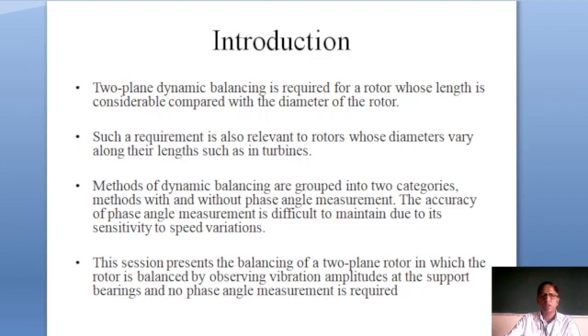The first category is with phase angle measurement and the second is without phase angle measurement. With phase angle measurement, we need to calculate the phase angle along with the vibration amplitudes at the support bearings, but phase angle measurement requires dedicated instrumentation. Different instruments are required for measuring the phase angle, and the correctness of the phase angle is also a point of discussion because the correct angle only comes when the speed is constant.